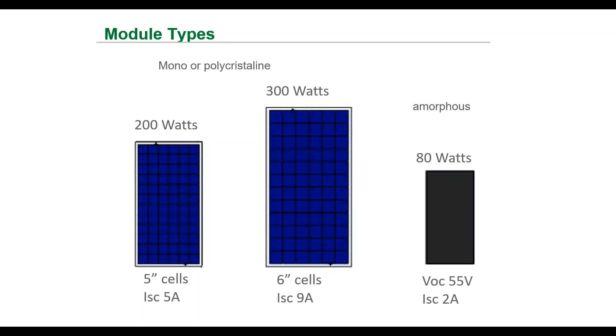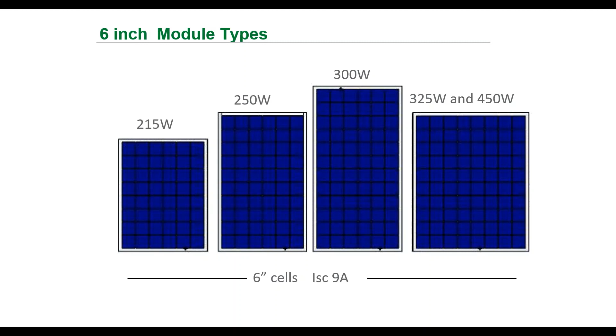So again, with 6-inch cells, ratings of 250, 300, even up to 450 watts exist, but 300 watt panels are predominantly used. Since it's a constant current source, we should always design the DC system for short circuit current. For example, if 9 ampere is your short circuit current, your cabling and switch gear should be designed for 9 ampere, not for your nominal current, which may be 7 or 6 ampere - that's maximum current. But you should design for short circuit current. If you design only for maximum current and a short circuit occurs, your entire cabling will burn and need replacement. To avoid that, design for short circuit current, or what we can call the absolute maximum.